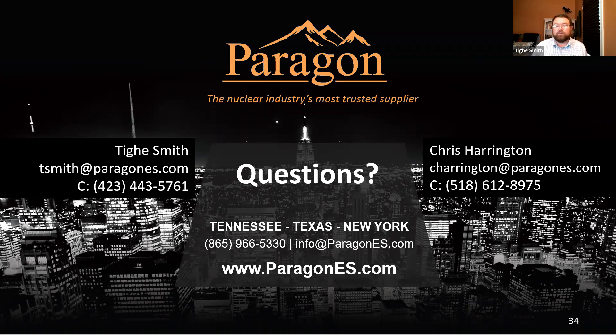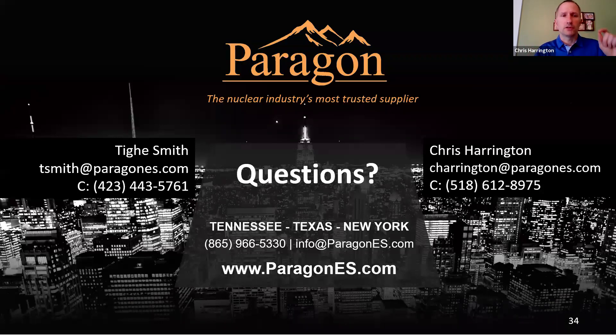Are we repairing any multi-layer printed circuit boards? If so, how do we figure out what the internal layers' connections are? That's one of the more challenging aspects with some more modern electronics that have both through-hole components and multi-layer circuit boards. You have to rely on having a schematic or being able to understand what that component connects to. In a multi-layer board with no information, the two internal planes on like a four-layer board are often just a ground plane and a power plane. If you can tell there's no trace you can see on top or bottom that goes anywhere, then it should be connected to one of those planes. Our full functional test evaluates the card at the input and output interface, so most or all of those should be covered through functional testing.